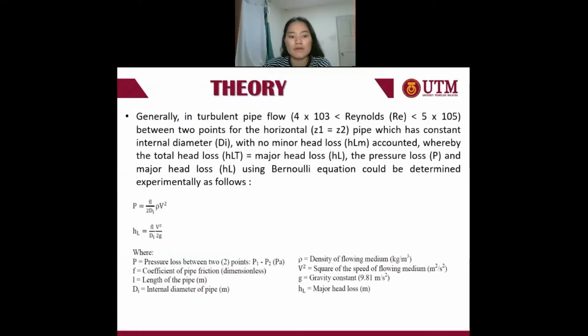For turbulent pipe flow between two horizontal points with constant cross-section and no minor head loss accounted, the total head loss is equal to the major head loss. The pressure loss and major head loss using the Bernoulli equation could be determined experimentally. Pressure loss is equal to the friction factor multiplied by rho multiplied by the square of speed, divided by 2 times the internal diameter.